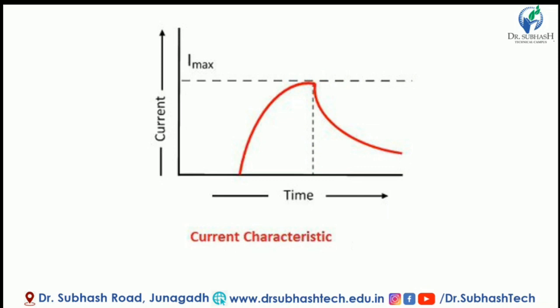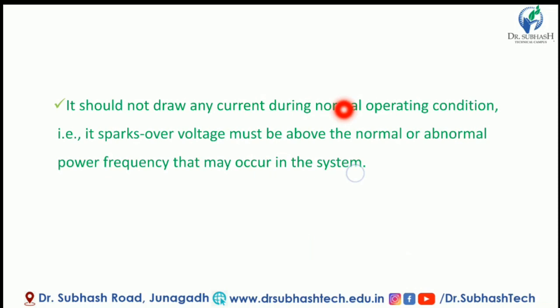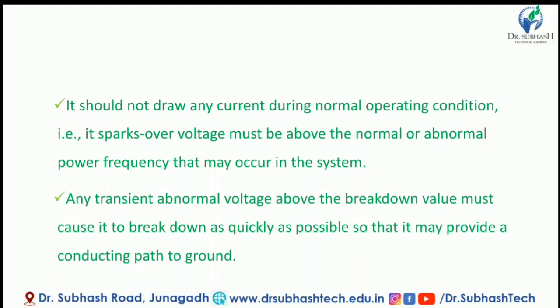The Lightning Arrestor should not draw any current during normal operating condition. The spark-over voltage must be above the normal or abnormal power frequency voltage that may occur in the power system. Any transient above the abnormal voltage — the breakdown value must cause it to break down as quickly as possible so that it may provide a conducting path to ground.